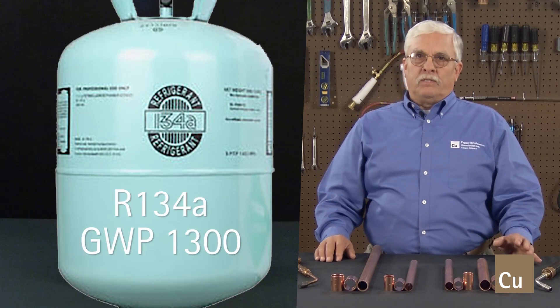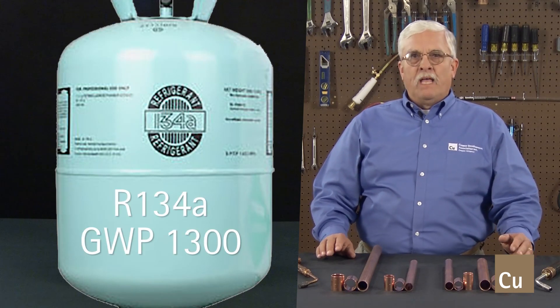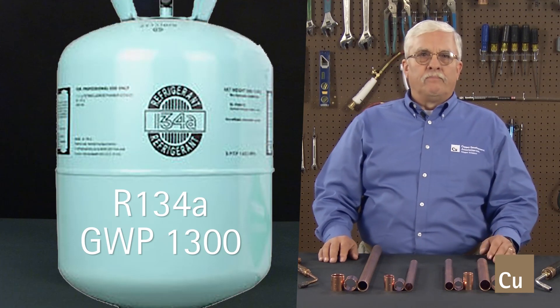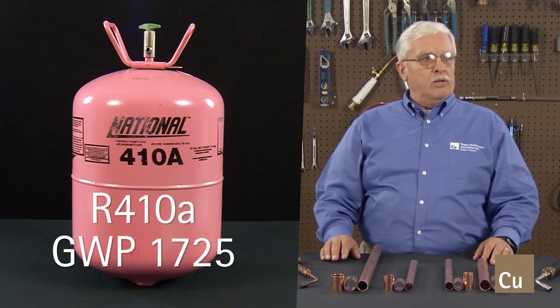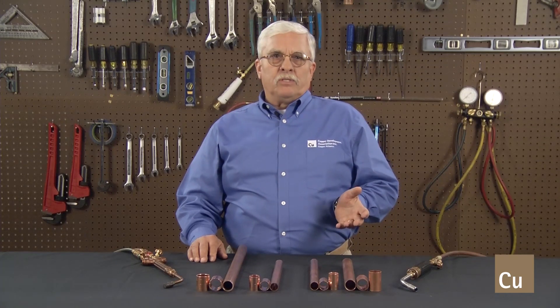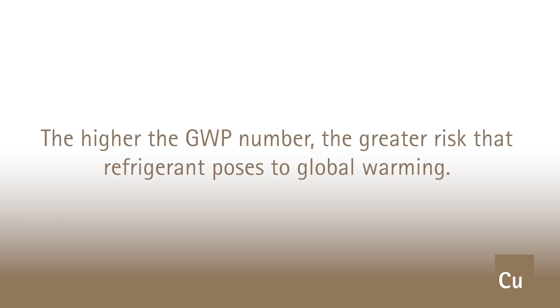R134A, a refrigerant developed as a substitute for R12, has a GWP of 1,300. And R410A, another replacement refrigerant, has a GWP of 1,725. GWP is the measurement of how much heat a greenhouse gas is capable of trapping in the atmosphere. The system compares the global warming potential of various gases, like refrigerants, to the baseline of carbon dioxide, which has a GWP of 1 and an ozone depletion potential, or ODP, of 0. The higher the GWP number, the greater risk that refrigerant poses to global warming.